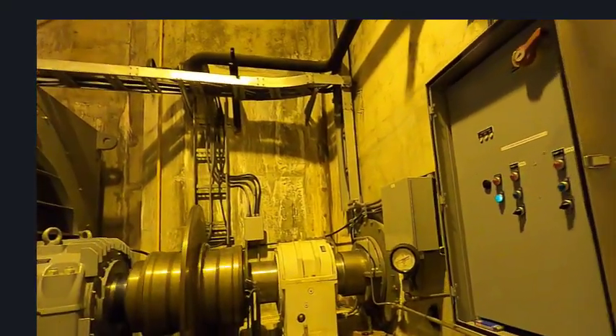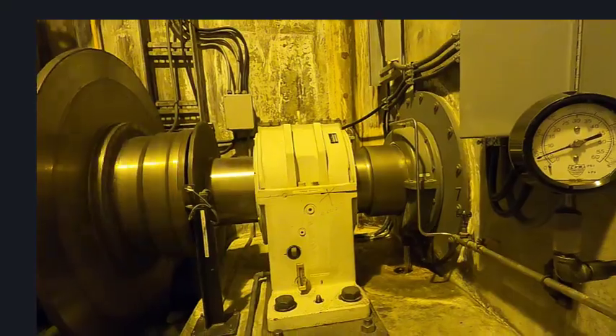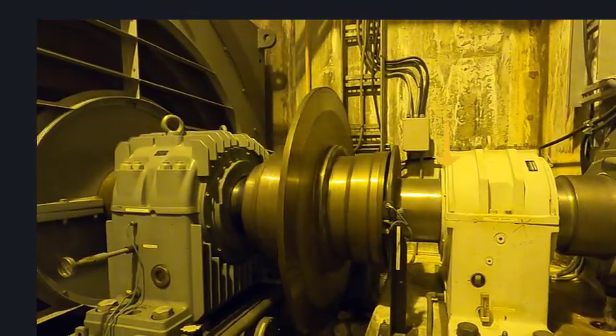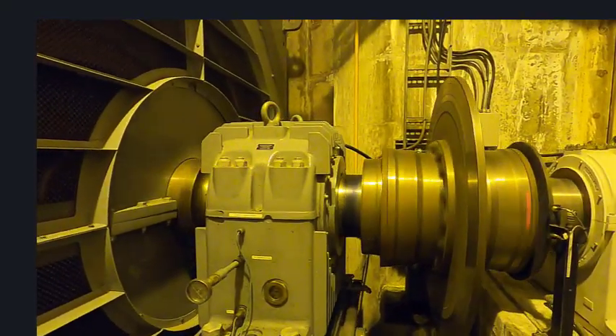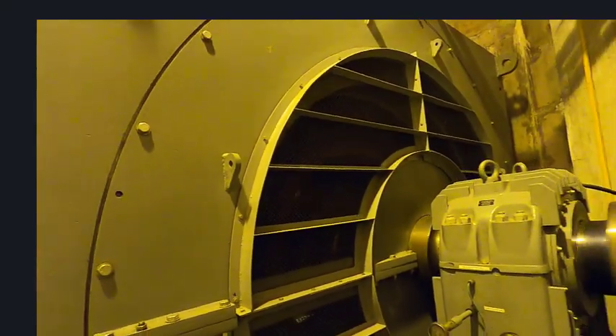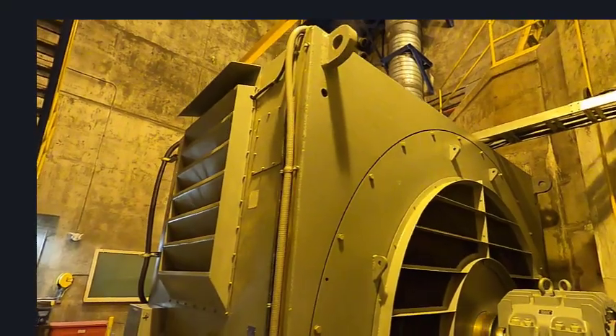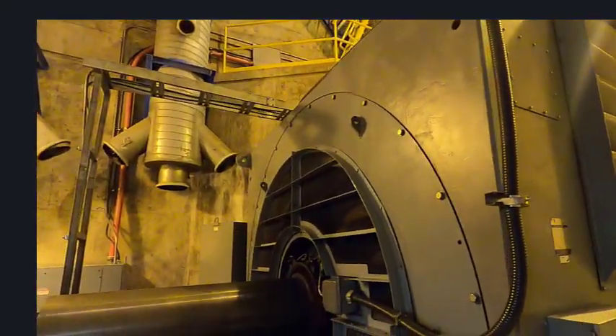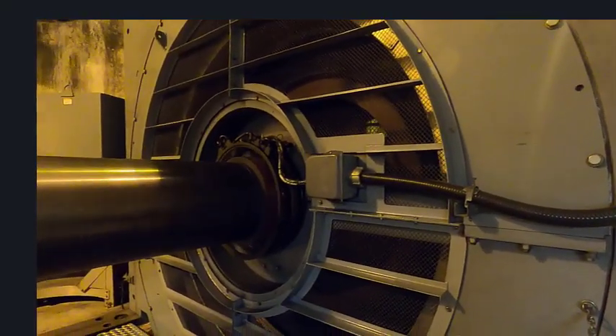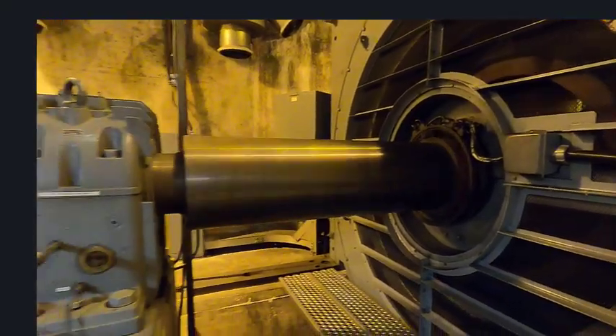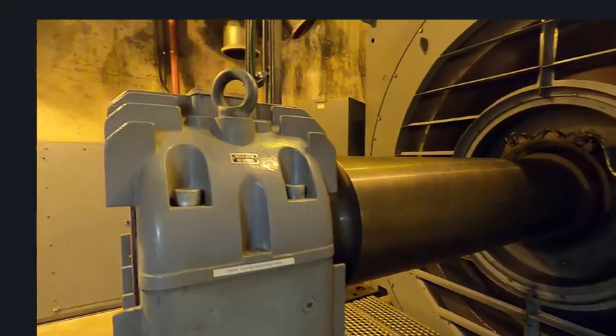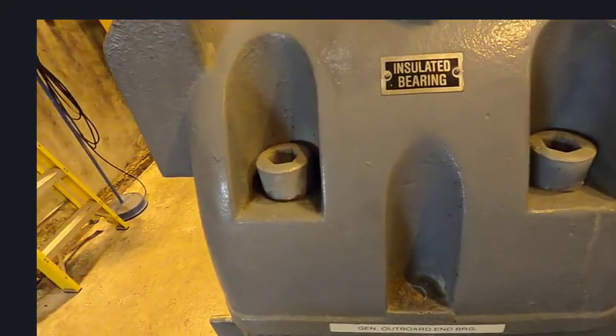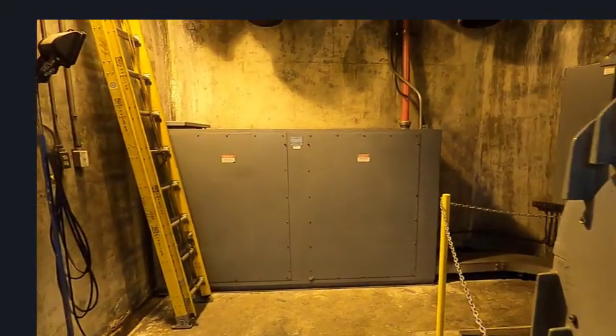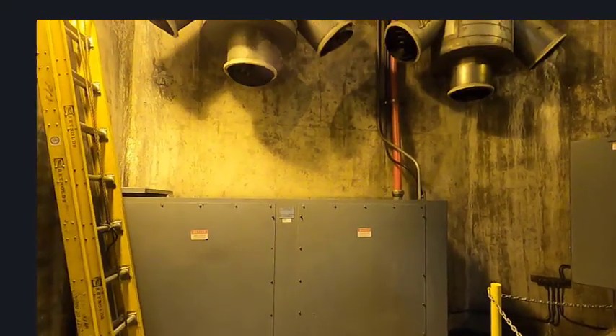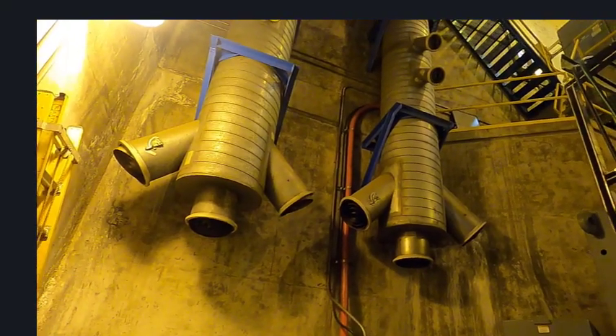Ahead of us here is the spinning shaft, rotating from the water flowing through the turbine. We can see a water seal to our far left, a friction bearing in its white housing ahead of us, and another friction bearing in the gray housing straight ahead. The large square box is the generator, which, as Kevin has mentioned, generates 12,000 volts phase to phase. Not very easy to see within the generator, but no different than generators 1, 2, 3, and 4, we have rotating magnets and stationary wires. Another friction bearing right ahead, and in the very background, we'll be able to see the wires leaving the building. There is the red Teck cable going up the wall and eventually out the building.